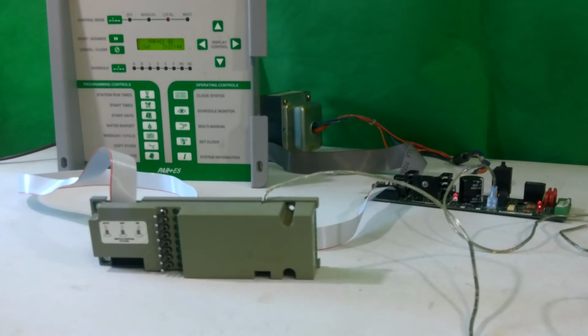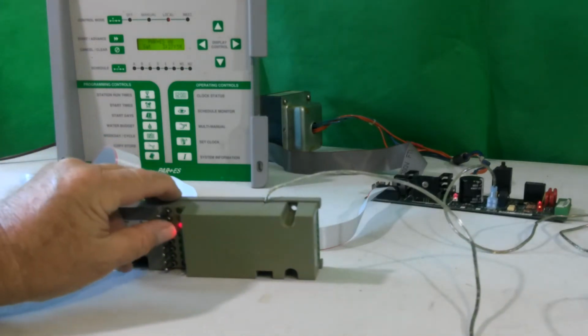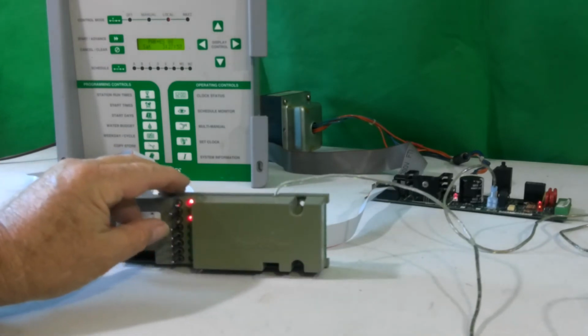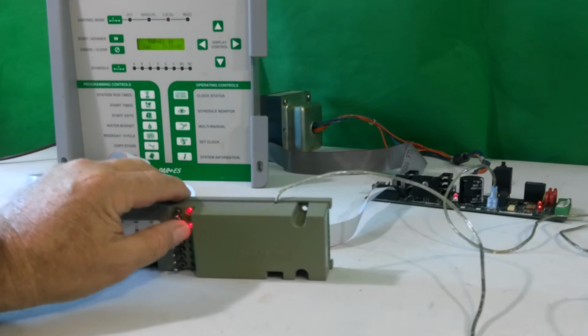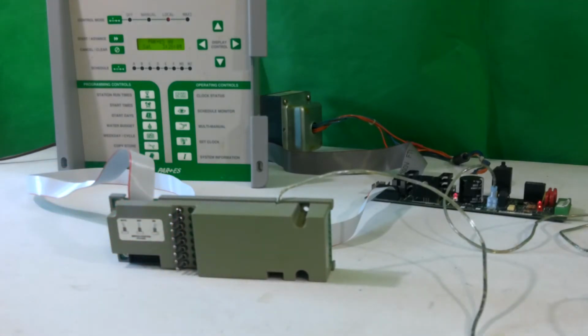If you turn on multiple stations and they do not turn on, again, check them by turning on at the switches, and should the lights turn on but they do not turn on in the field, it says we have multiple components out and the thing needs to be sent in for repair.